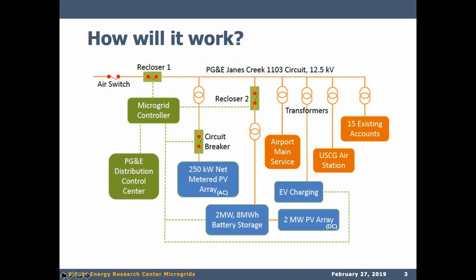Recloser 1 is the islanding recloser, so it will disconnect the microgrid from the main grid and put it in island mode, and recloser 2 is the generation recloser that can isolate the 2 megawatt battery and 2 megawatt PV array from the system. In blue sky operation, both of those reclosers will be closed. That'll be most of the time. The net metered array will be credited to the airport account. The 2 megawatt array and battery storage will be interconnected and offered up in the CalISO market, and everything will be running in parallel with the main grid.